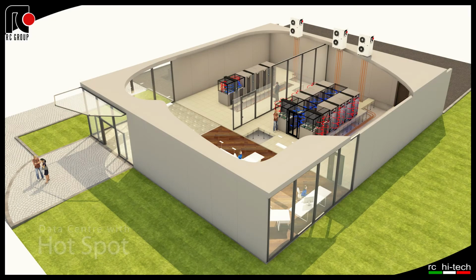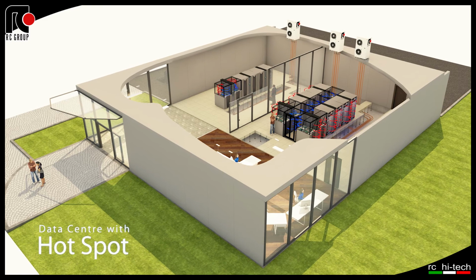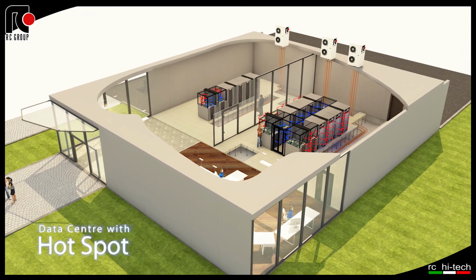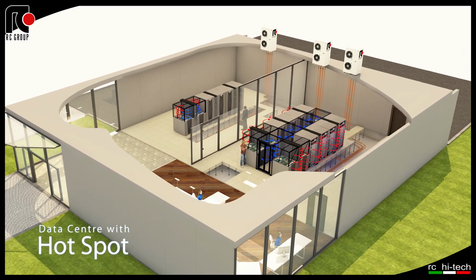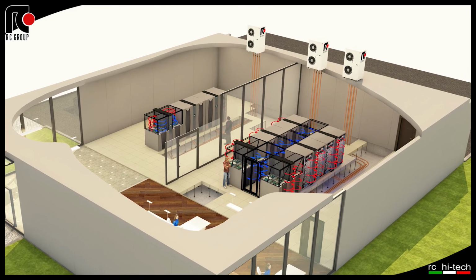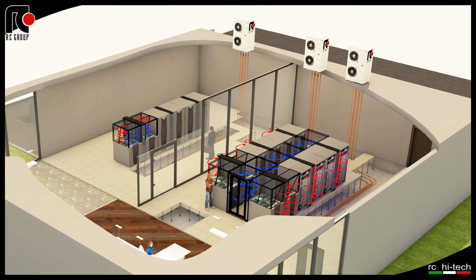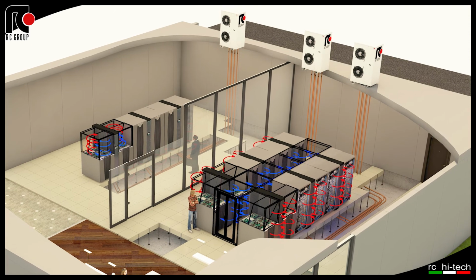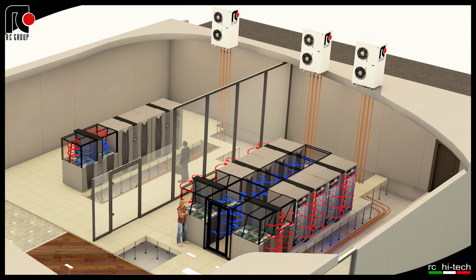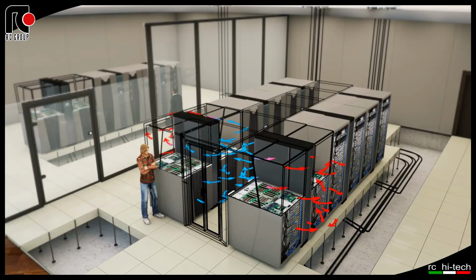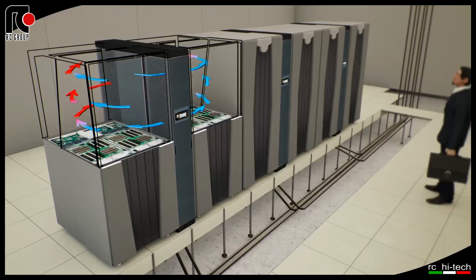Data center with hotspot. For data center hotspots with areas of high concentrated thermal loads, the best solution is represented by the direct expansion cool site system, consisting of indoor DX evaporator units and outdoor air-cooled motocondensing units. The indoor units are equipped with EC plug fans and are available with 2 airflow options: in row for installations with hot aisles and cold aisles, in rack with air supply and return inside the rack.